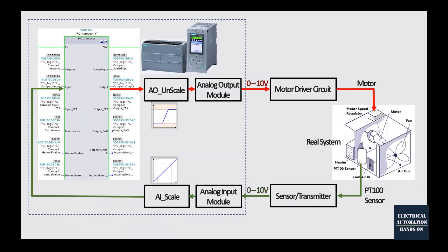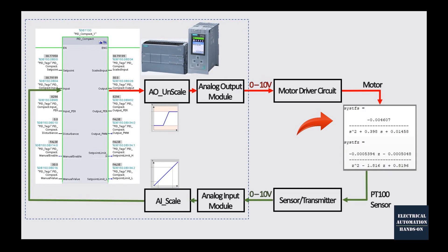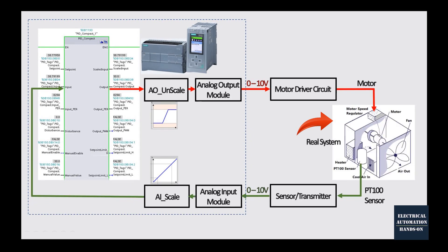If you already have the mathematical model of your controlled object, you can use your PLC PID controller to connect to this mathematical model and use it as your process object to test the PID gain, integral, and derivative parameters. And once the construction on site is finished, you can switch the system to the actual process.